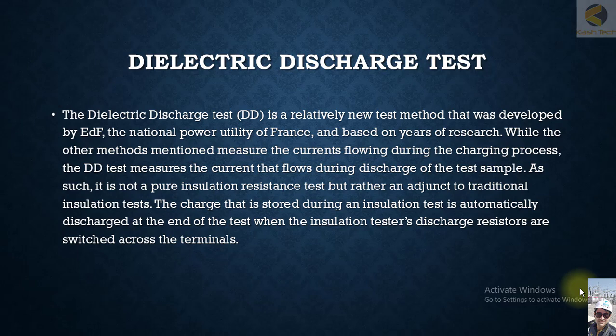Normal testing methods measure the charging current — when you are applying voltage, they measure the current, and there will be some leakage current, resistive current, charging current, surface leakage current, or polarizing current. All these components are measured during the charging process.